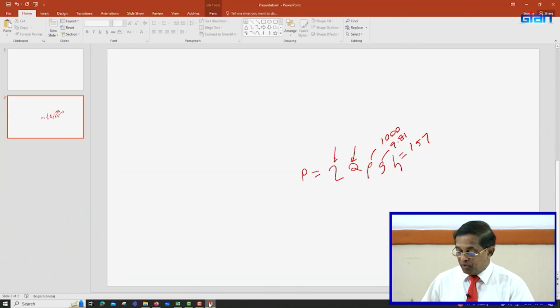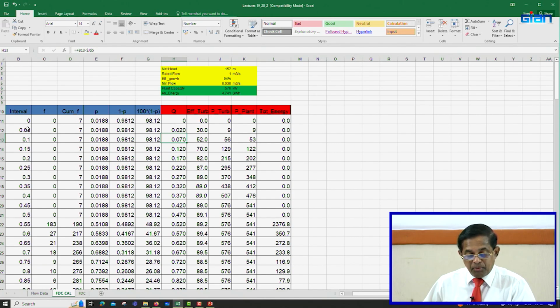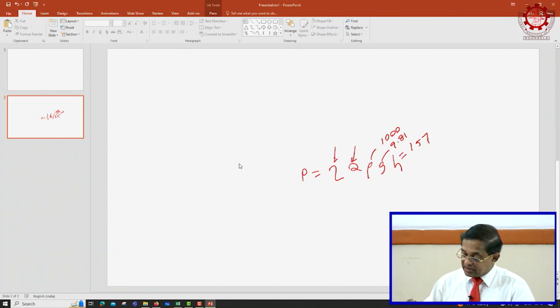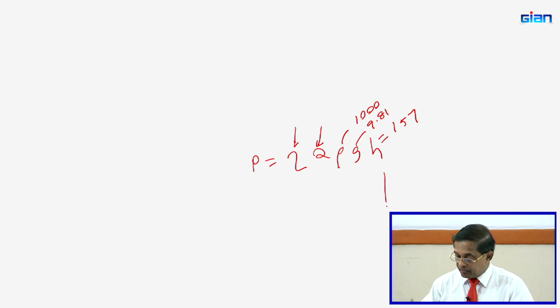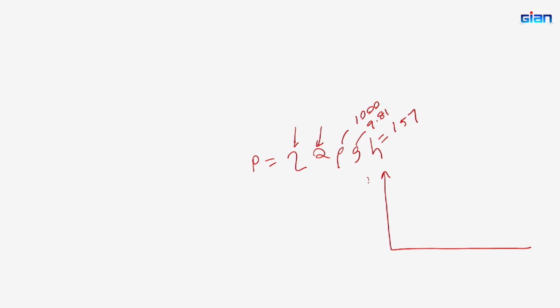So, we have got the Q now. We want to get the Q for a given time and then we want to know the efficiency at that point. So, when the flow is 0.05, Q is this, then how can we get the efficiency of the turbine? That we have to get from the curve that we discussed earlier. We looked at the efficiency curves with Q flow. If it is a Francis turbine, it will be something like this. We have to know our flow rate, say 0.02, and then we can get the efficiency point.